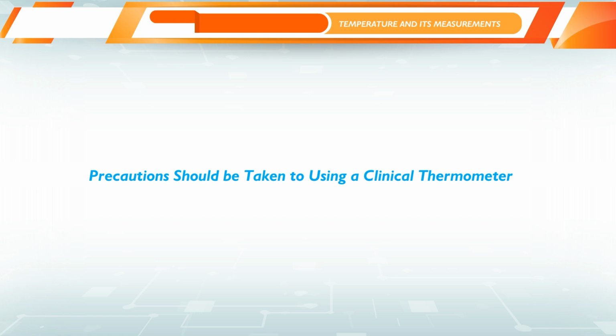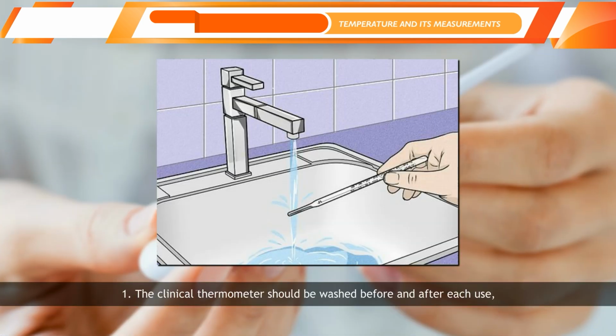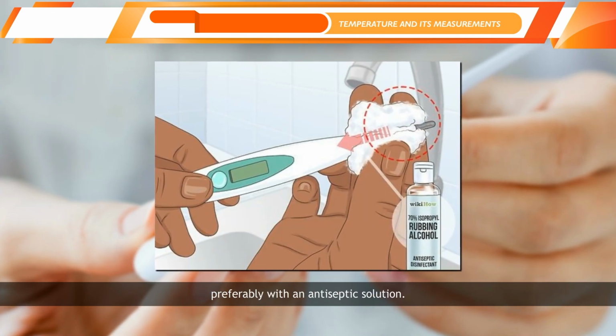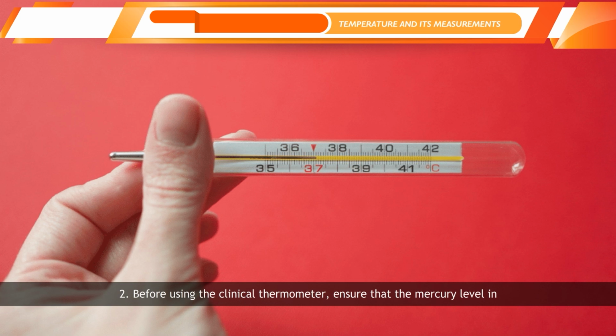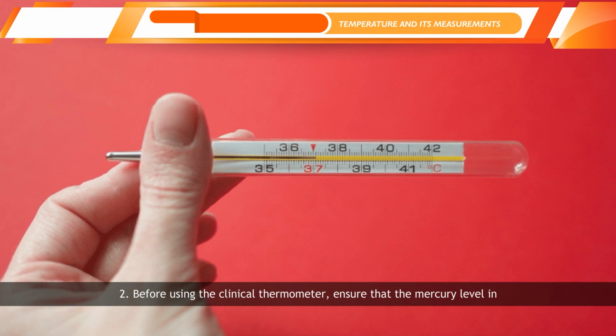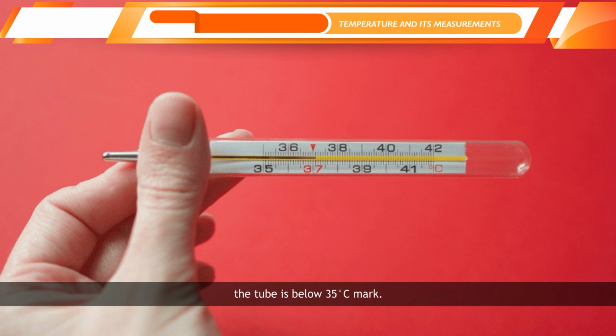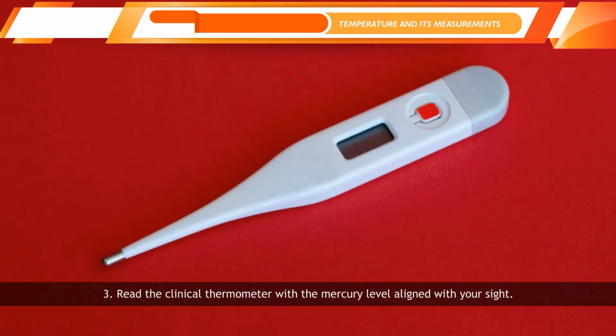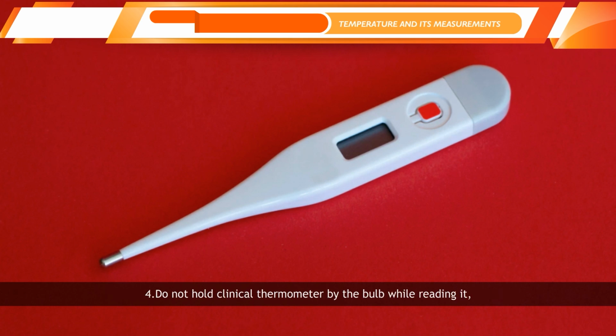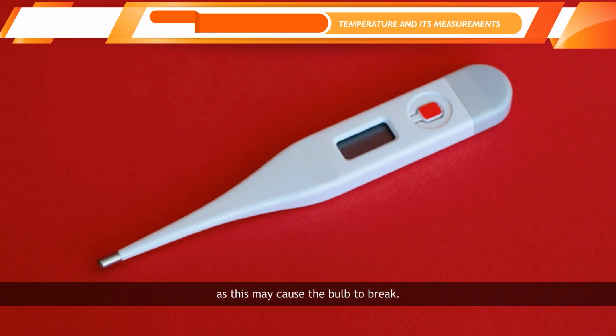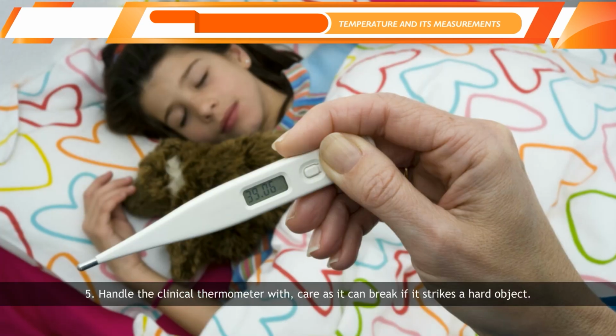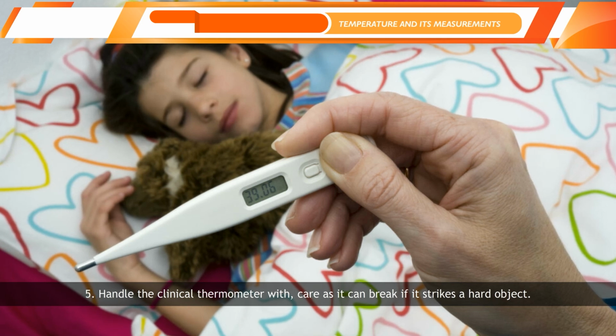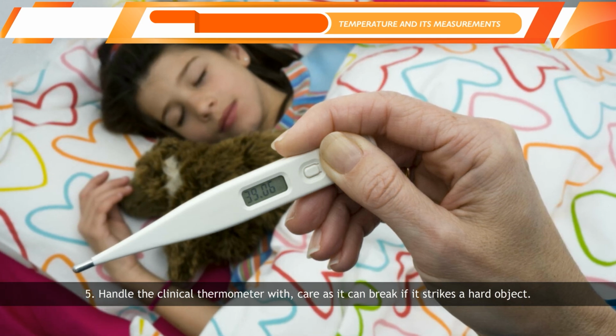Precautions should be taken when using a clinical thermometer. 1. The clinical thermometer should be washed before and after each use, preferably with an antiseptic solution. 2. Before using the clinical thermometer, ensure that the mercury level in the tube is below the 35 degrees Celsius mark. 3. Read the clinical thermometer with the mercury level aligned with your sight. 4. Do not hold the clinical thermometer by the bulb while reading it, as this may cause the bulb to break. 5. Handle the clinical thermometer with care as it can break if it strikes a hard object.